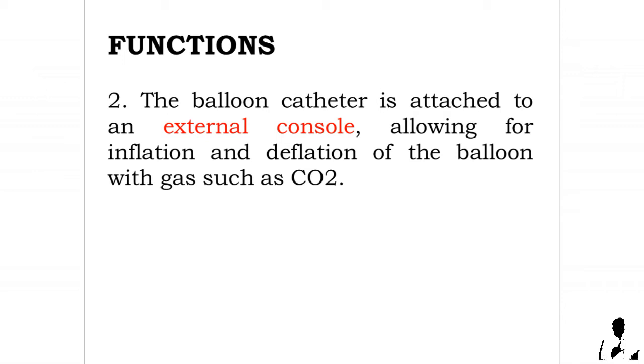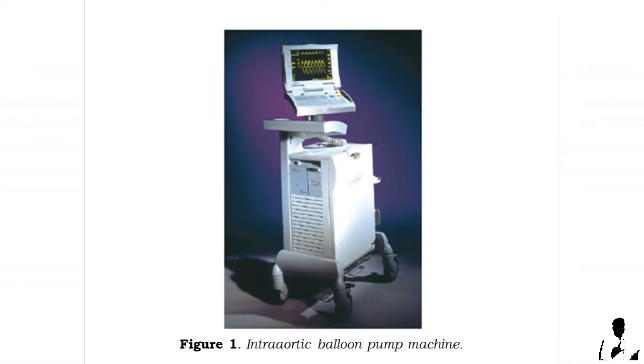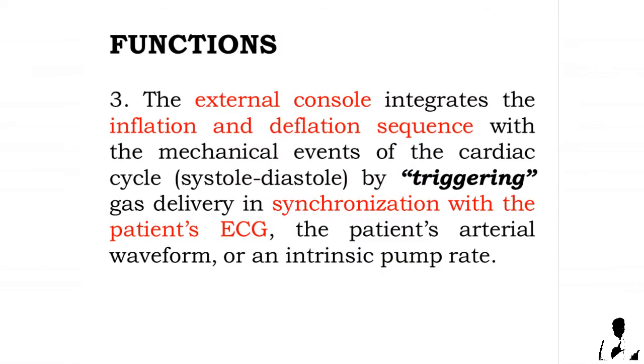Three, the external console integrates the inflation and deflation sequence with the mechanical events of the cardiac cycle — systole and diastole — by triggering gas delivery in synchronization with the patient's ECG, the patient's arterial waveform, or an intrinsic pump rate.